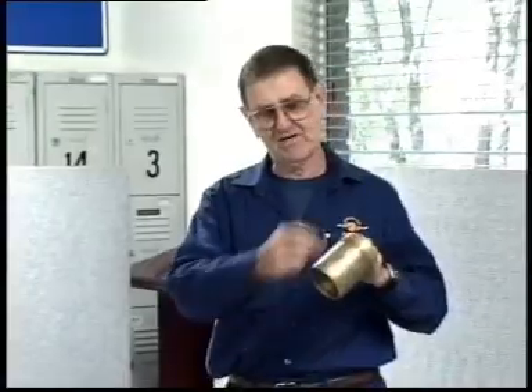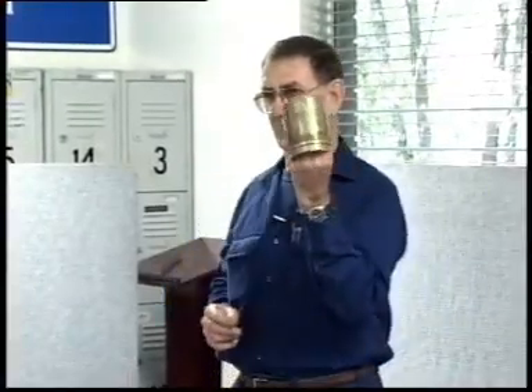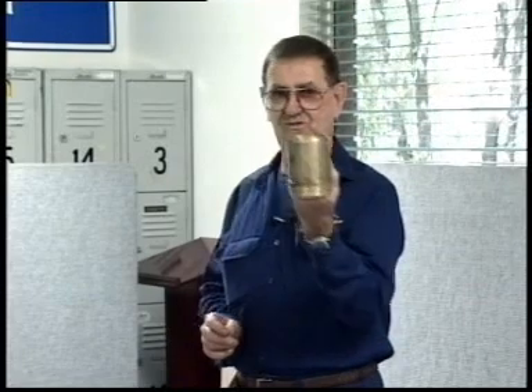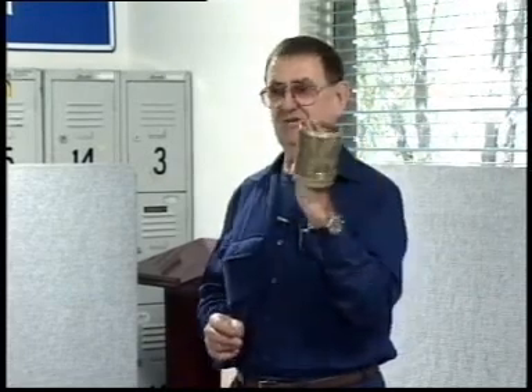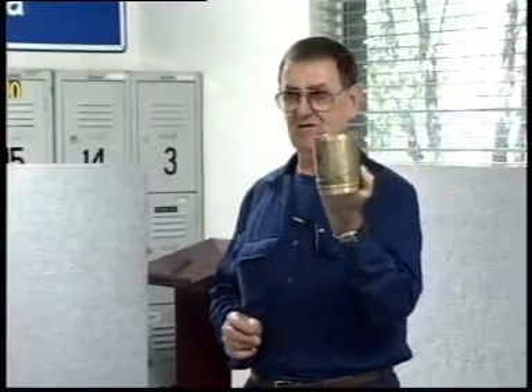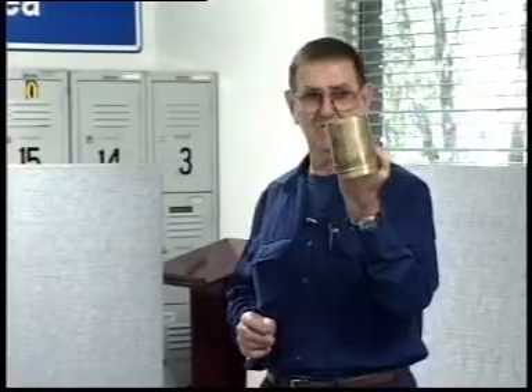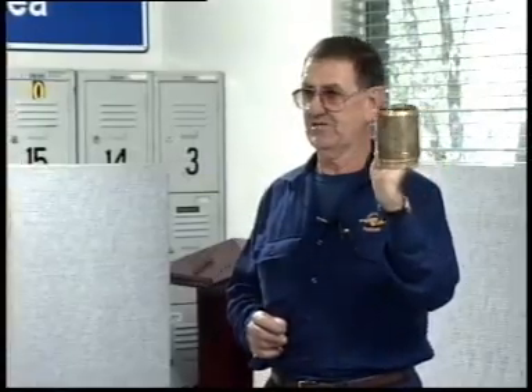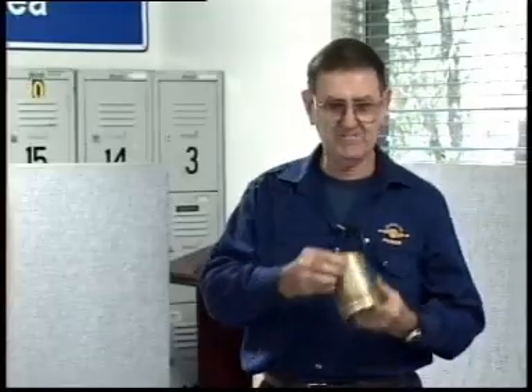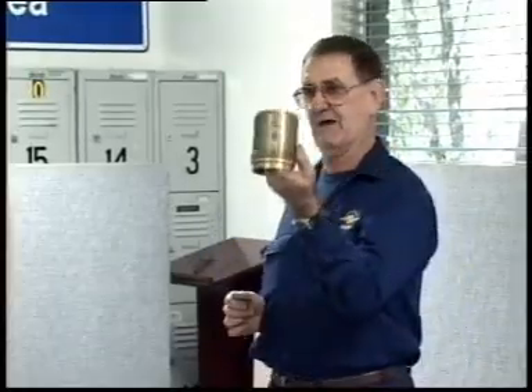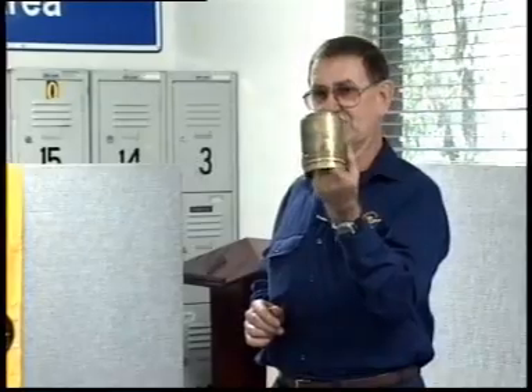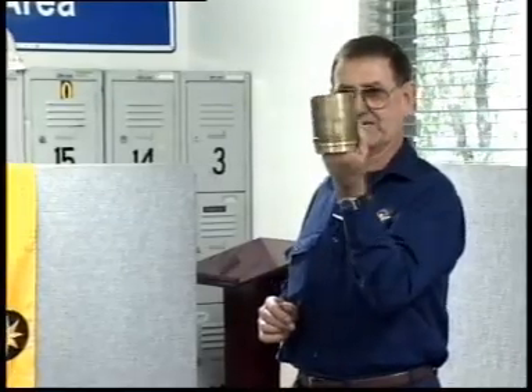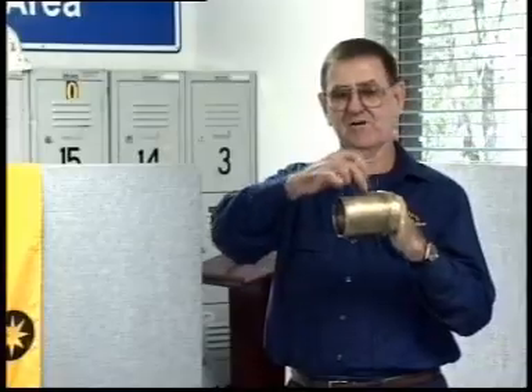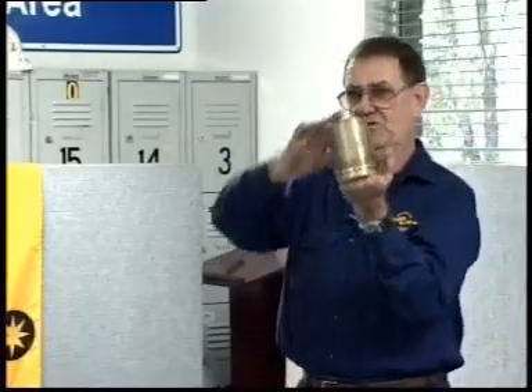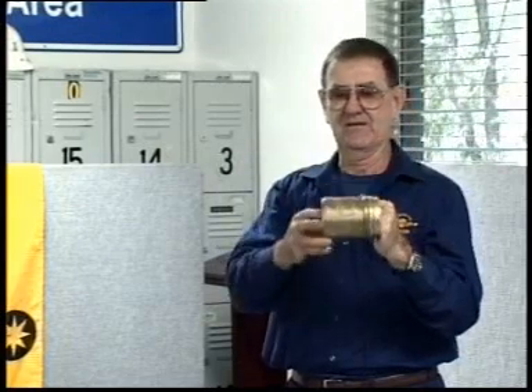Now, if that scratch is running long ways along that flame path, then it probably does not comply, and it should be changed out. If you can't make the determination yourself, and just use common sense, see somebody who should be able to, like your electrician or your deputy or whoever, to make sure that they can make the determination. On the other side, if you turn it over, I've put some indentations in the flame path with a hammer. They also don't pass, just to show you that there's a couple of different styles of things that can happen to them. So if the flame can hop, skip and jump up some of these little valleys, it could be hot enough by the time it got outside to create a problem. So I've damaged that one.